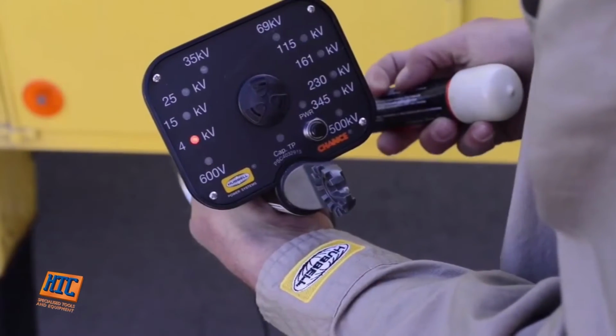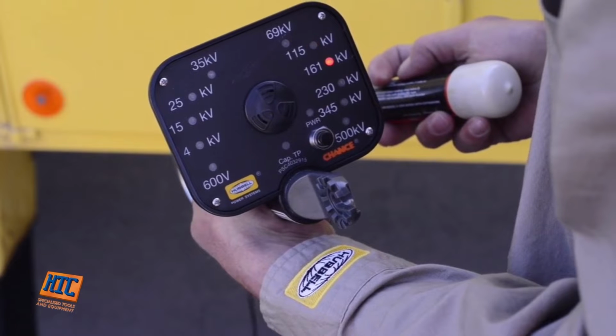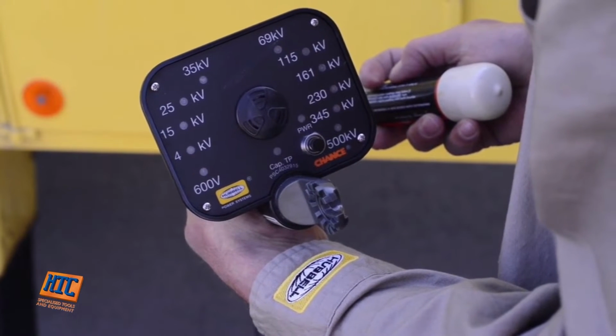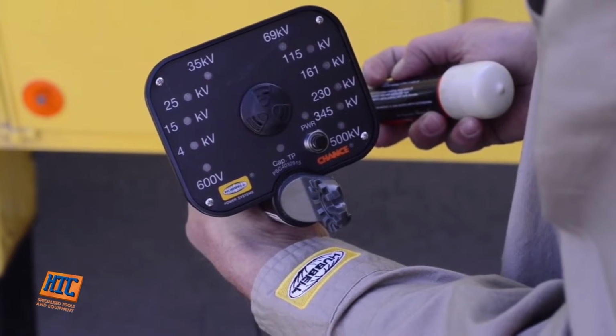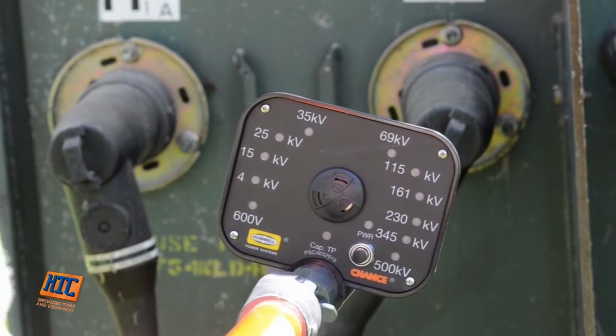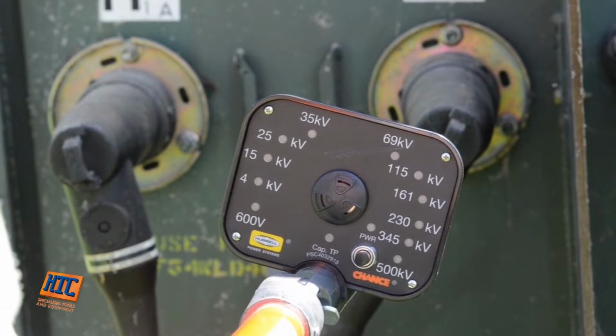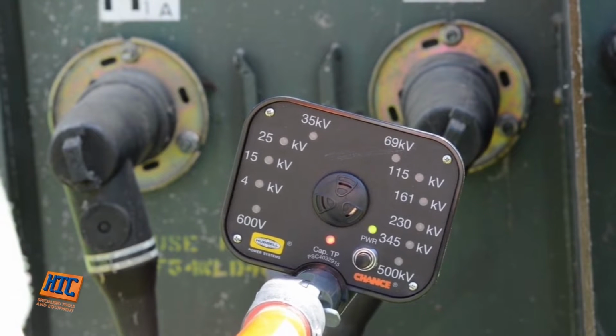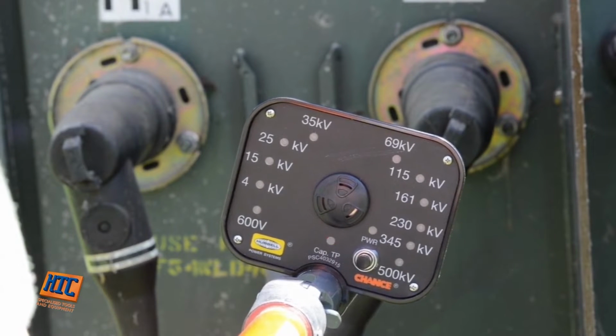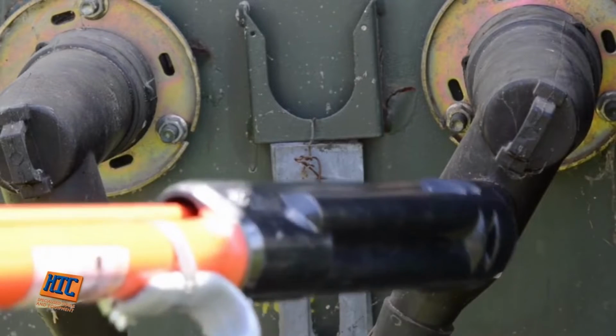After each use, verify the RV is fully functional, again using the voltage indicator tester specified in the instructions provided with the RV. The RV can also be used on underground circuits. Here's how it works to check for voltage at a 200 amp load break elbow with a capacitance test point. The cap covering the test point is removed using an insulated hot stick.